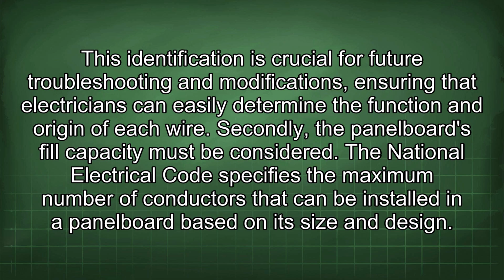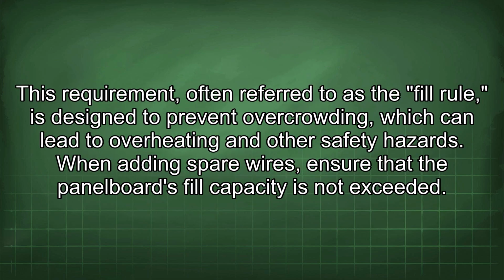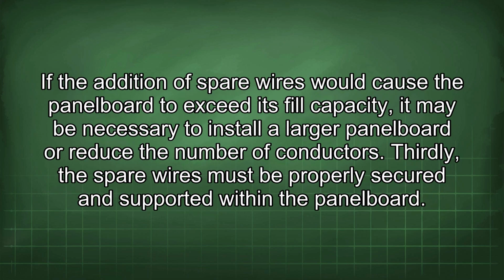each wire. Secondly, the panel board's fill capacity must be considered. The National Electrical Code specifies the maximum number of conductors that can be installed in a panel board based on its size and design. This requirement, often referred to as the fill rule, is designed to prevent overcrowding, which can lead to overheating and other safety hazards. When adding spare wires, ensure that the panel board's fill capacity is not exceeded. If the addition of spare wires would cause the panel board to exceed its fill capacity, it may be necessary to install a larger panel board or reduce the number of conductors.